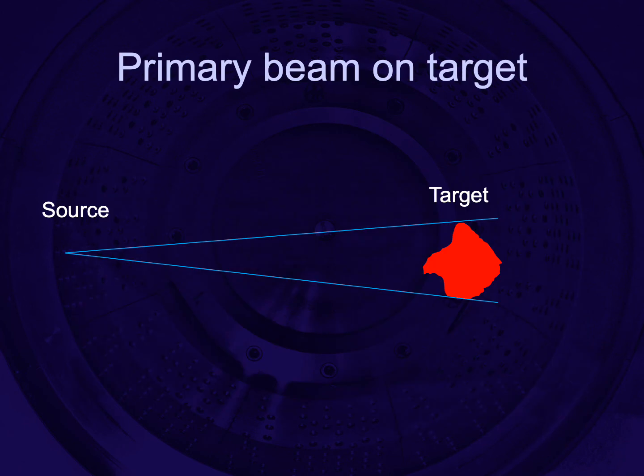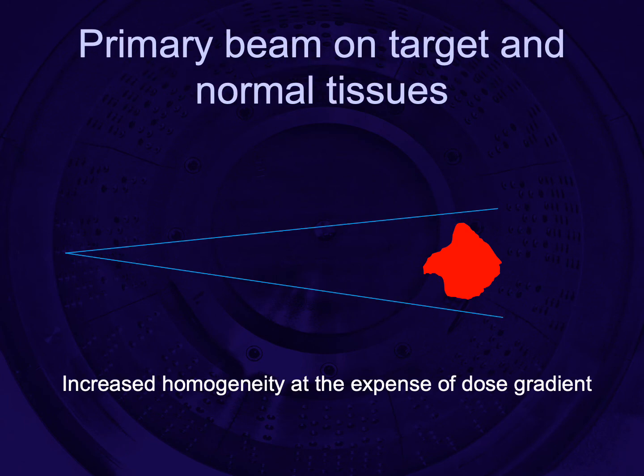If we have our radiation source and our target, one approach is to ensure the edge of the beam just touches the edge of the target — this gives the steepest dose fall-off possible. What is often done with some radiosurgery technologies is to open up the beam a bit, which increases homogeneity inside the target but at the expense of dose gradient.